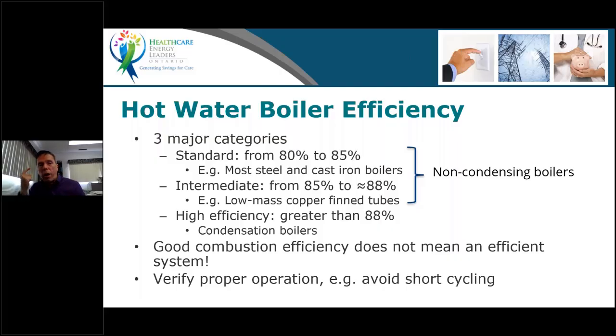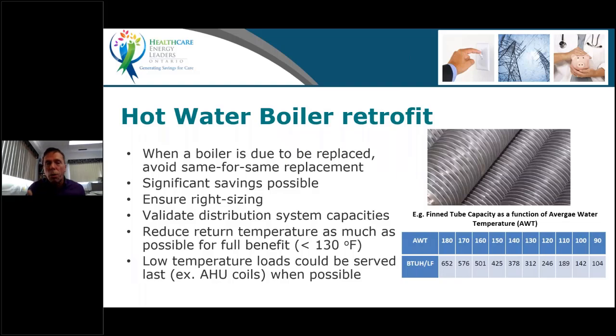And the other thing you have to be very careful about, you get more losses from that than you would from optimizing your excess air, is short cycling. A boiler that starts and stops will lose significant efficiency because there's always a purge cycle. You will actually lose significantly more if you have a boiler that keeps starting and stopping all the time. And there's, again, various reasons why it might do that. So you really need to have it looked at if you consider that it is short cycling.